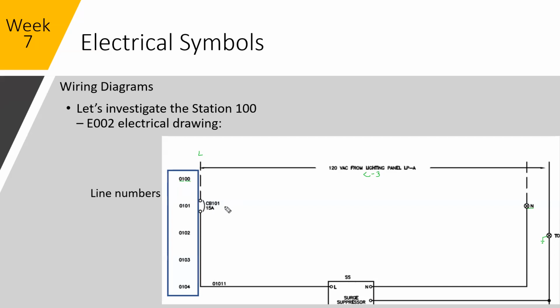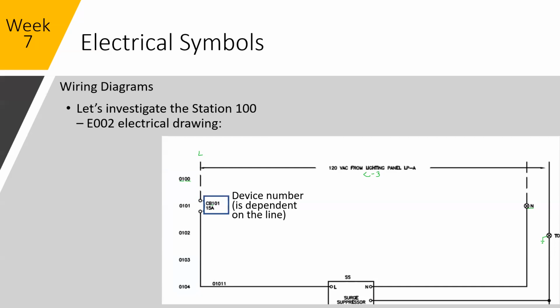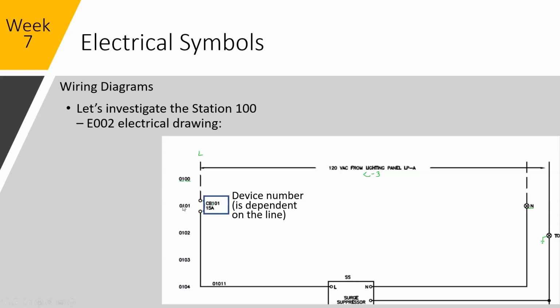So CB101, if you set your drawings up properly and you've built your panel properly, in my opinion and that of whoever designed this. If you look at circuit breaker 101, what we're indicating here is that on page 1, line 1, you'll be able to find your information for where that circuit breaker is. Good drawings with well-labeled devices, which correlate to tags on devices and panels, make for better and easier troubleshooting. So the device number is dependent on the line number. So CB101, 0101.